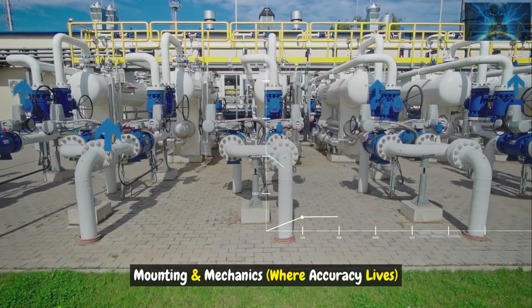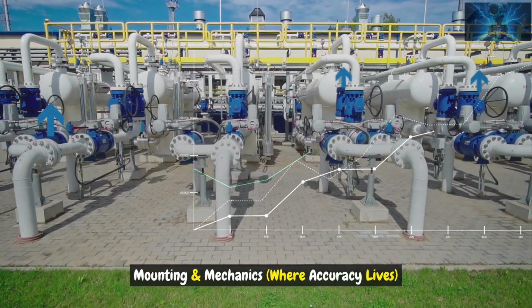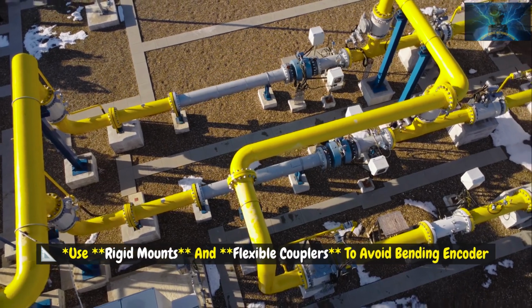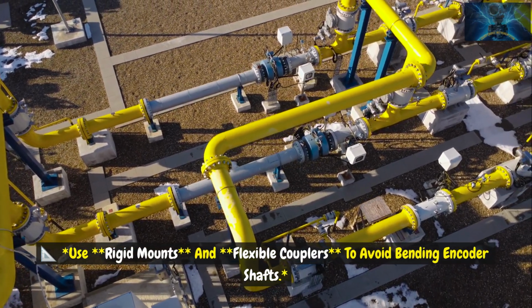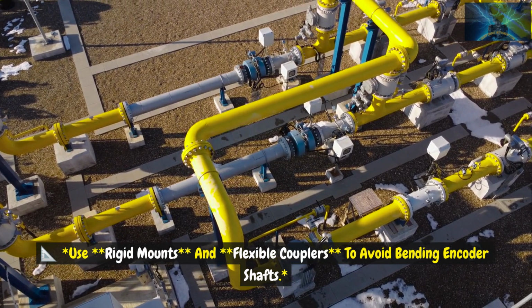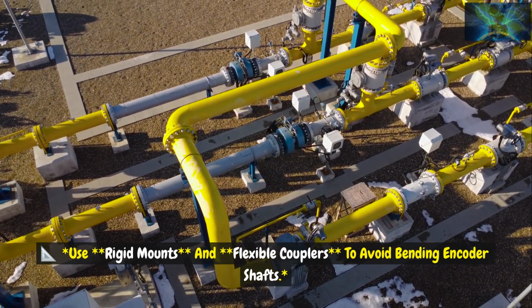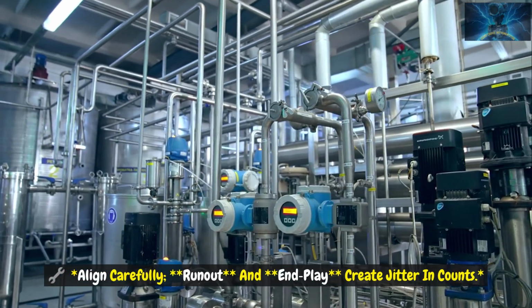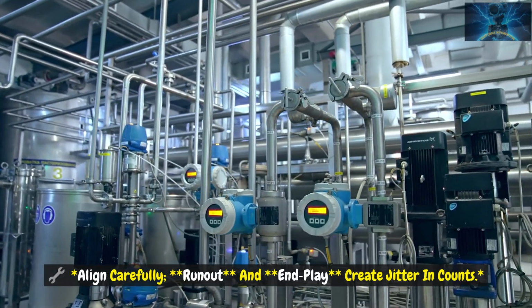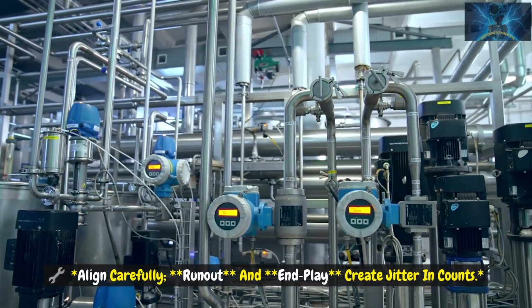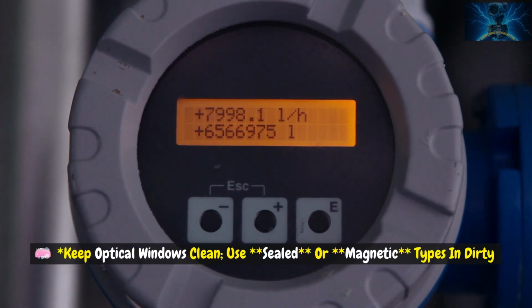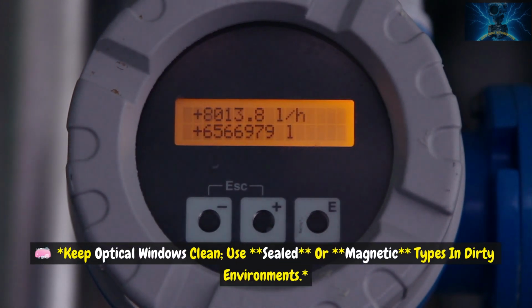Mounting and mechanics, where accuracy lives. Use rigid mounts and flexible couplers to avoid bending encoder shafts. Align carefully. Runout and play create jitter in counts. Keep optical windows clean. Use sealed or magnetic types in dirty environments.